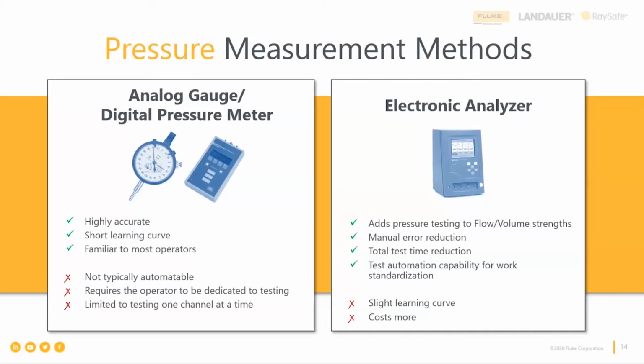The rest of the benefits of using an electronic analyzer as a method of pressure measurement would be very similar to what we just discussed for volume and flow rate. Again, it reduces manual error. It reduces the time for completing the test. It allows for work standardization because of the test automation in it. And it's just the same setup that you're using for the entire test procedure and test setup, so it's highly convenient. And then again, the weaknesses could be the same. There's still some learning curve to it that could be mitigated by using software, and the price is higher than the other setup.